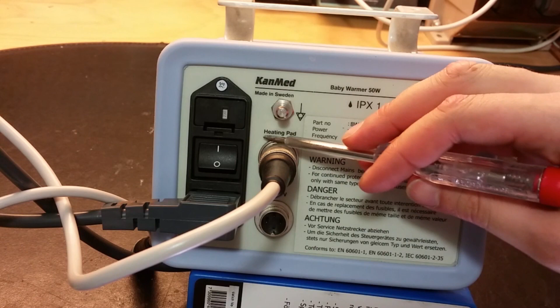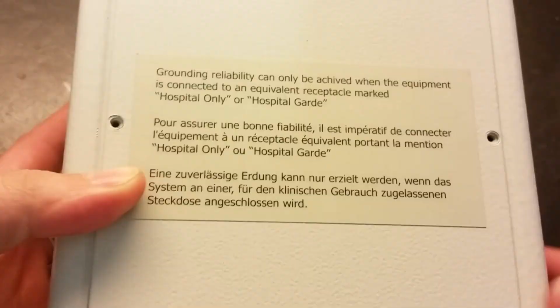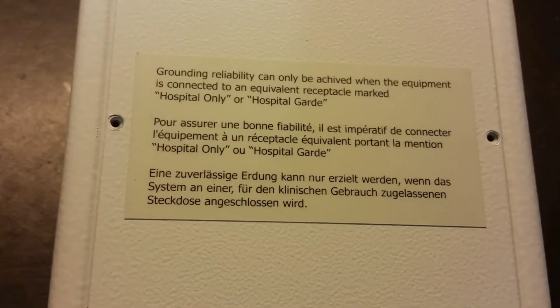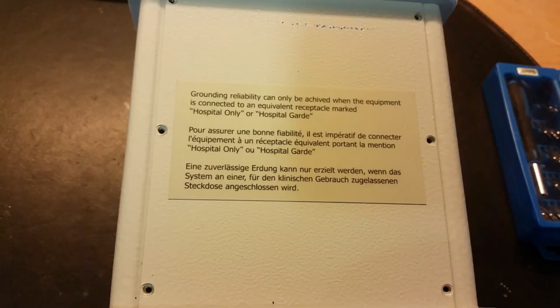On the back here it even says that ground reliability can only be achieved when the equipment is connected to an equivalent receptacle marked hospital only or hospital grade. And they're of course meaning that ground tap here.